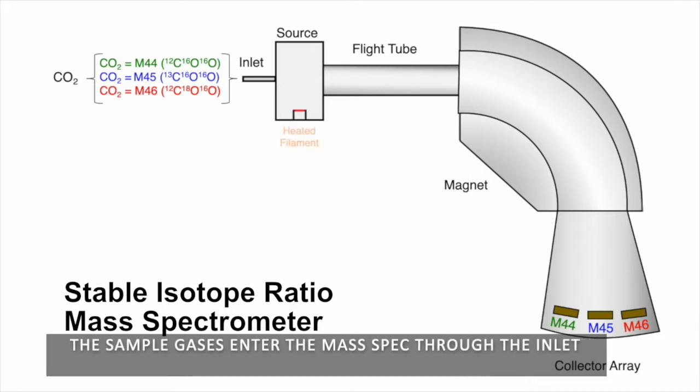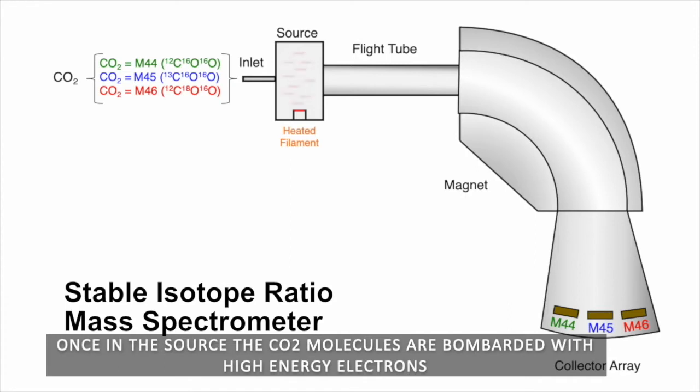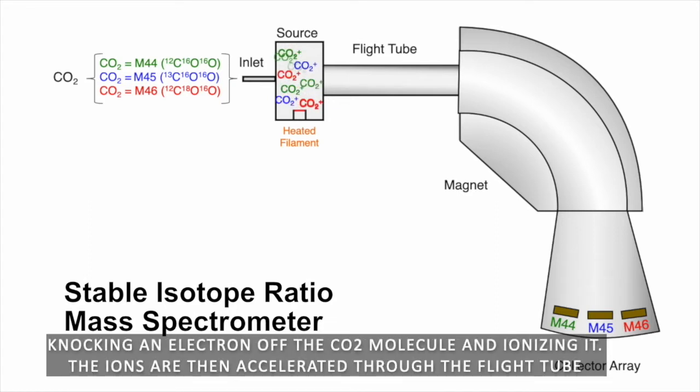The sample gases enter the mass spec through the inlet. Once in the source, the CO2 molecules are bombarded with high energy electrons, knocking an electron off the CO2 molecule and ionizing it.